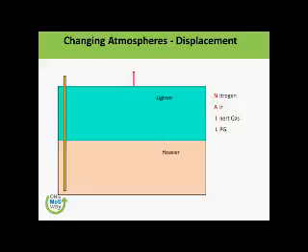So I'm not telling you anything about the methane, which is your LNG. There is a very strange phenomenon with methane: methane is lighter than air when it is above minus 100 degrees centigrade, and it is heavier than air when it is below minus 100 degrees centigrade.